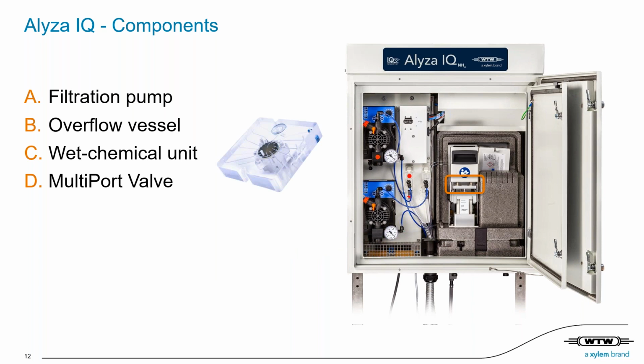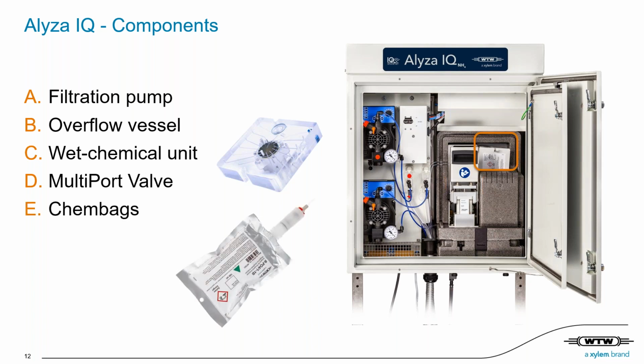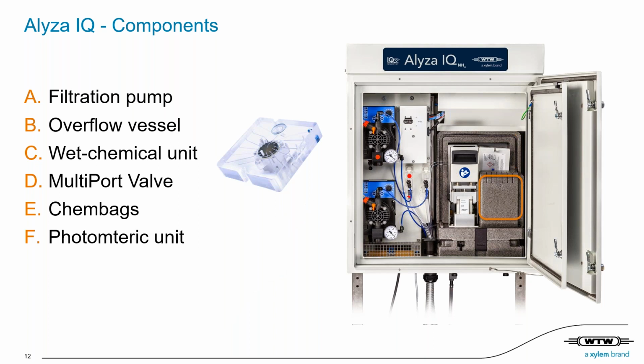Inside the wet chemical unit, the core parts of the new analyzer are located. Here in orange, you can see the location of the MultiPort valve, the heart of the analyzer. This is the location of the so-called ChemBags, which contain the reagents. I'll come to the two core components in a few seconds. And last but not least, this is the wet chemical photometric unit. It is also insulated to help speed up the reaction and increase the measurement accuracy by a constant higher temperature.